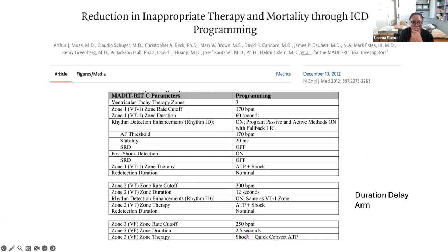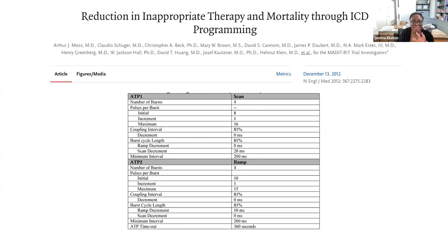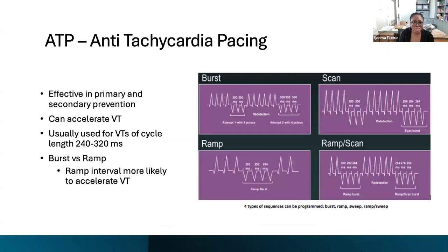And then in your zone three, they actually programmed a VF zone, which was greater than 250 milliseconds, and that one was 250 beats a minute. You had your zone duration be at 2.5 seconds and you shocked after that. So what they found, and in addition to that, they also had different arms for ATP, where in certain cases they would program a lot more ATP, or they would increment or change their programming a little bit. And you can see more in the paper.